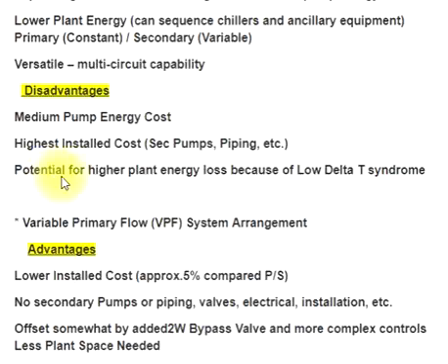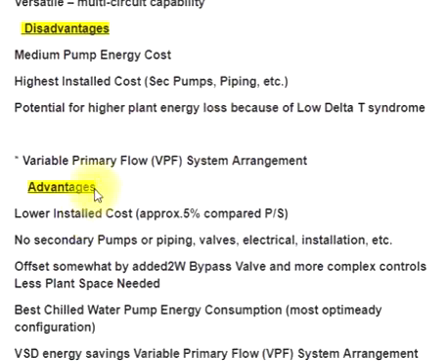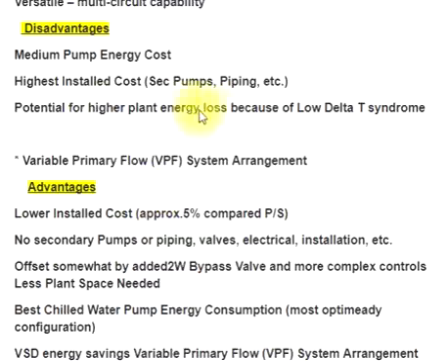Primary-secondary disadvantages: medium pump energy cost, highest installed cost due to secondary pumps, piping, etc., and potential for higher plant energy loss because of low delta-T syndrome.